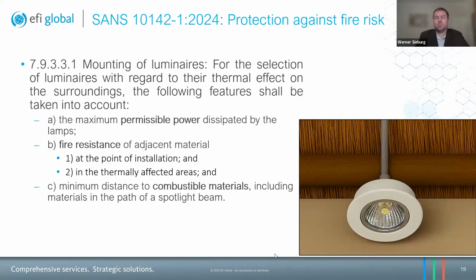So the following features shall be taken into account, and here I just wish to pause again to say, very often a standard is quite prescriptive in terms of what you can do, what you cannot do. What the end of this clause basically states is that the designer or the person that wires this premises needs to take into account, in other words, he needs to make a rational decision in terms of the amount of heat that is expected from a light. And so the position of this light currently in close proximity to the thatch, to me, is irresponsible.